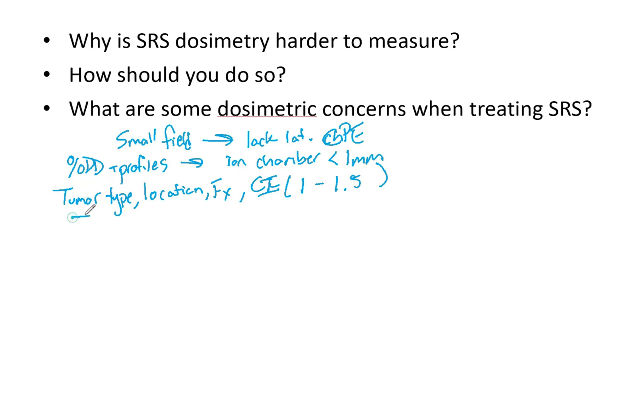You'll want to reference TG-101 for SBRT and TG-42 for SRS QA. Additional concerns include intermediate and low dose spilling — because using multiple arc and field angles to treat these tumors means low dose may spread throughout portions of the brain. Many physicians also look closely at normal brain dose, and there are protocols and task groups that specify what normal brain dose should be.